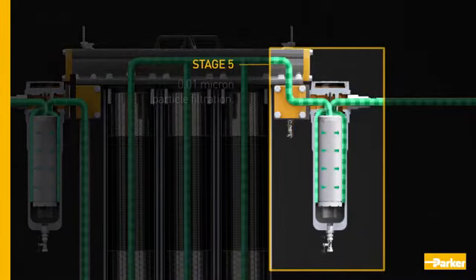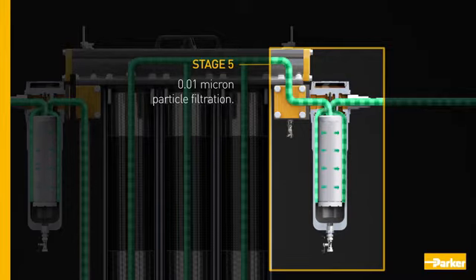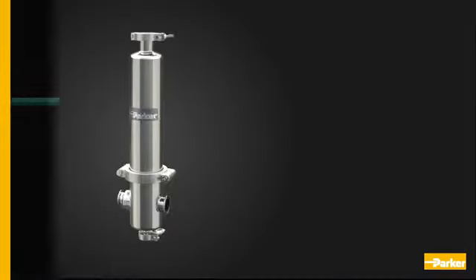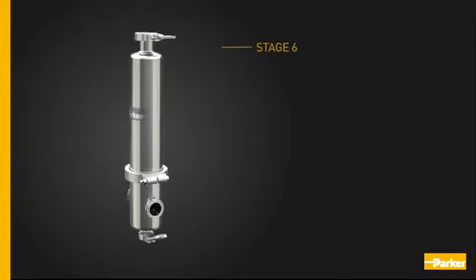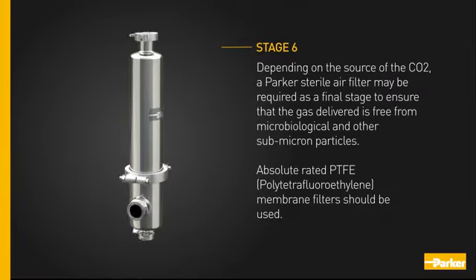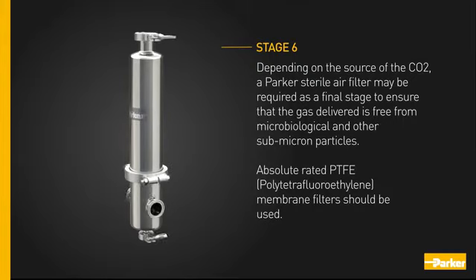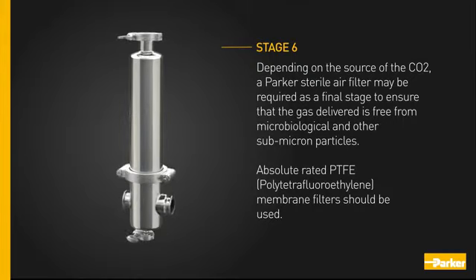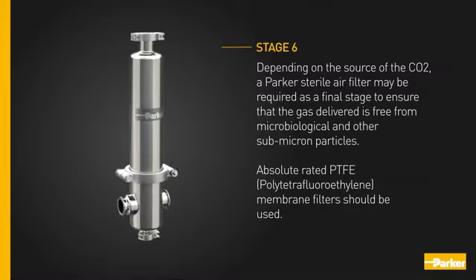Stage 5: 0.01 micron particle filtration. Depending on the source of the CO2, a Parker sterile air filter may be required as a final stage to ensure that the gas delivered is free from microbiological and other sub-micron particles. Absolute-rated PTFE membrane filters should be used.